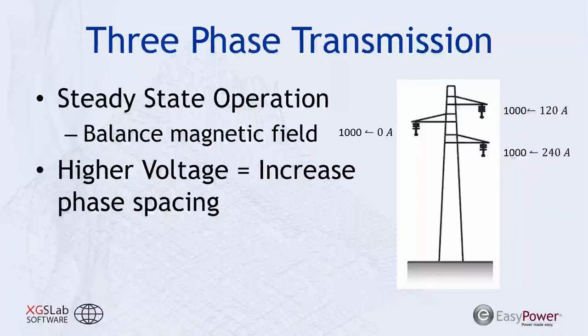And because we're talking about AC interference as it relates from a transmission line to other objects nearby, in our power system, we use three-phase balanced systems, and that means that we're going to have balanced current on each of our phases, which results in a balanced magnetic field. But the difference is that the magnetic field strength is going to be dependent on its relationship or its distance from each phase conductor. So if you are able to make each phase conductor tighter, you're going to see a greater cancellation in the magnetic field. But if you are having each of those phase conductors spaced farther apart, like you would for higher voltages, you're going to see greater magnetic fields resulting along that transmission line.